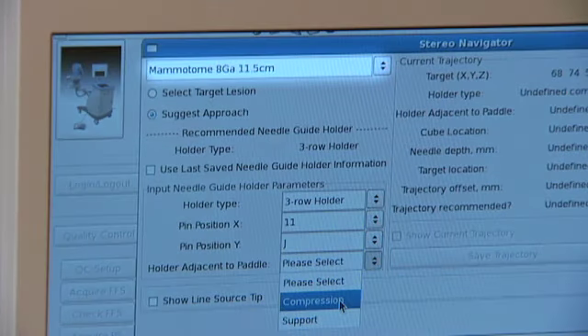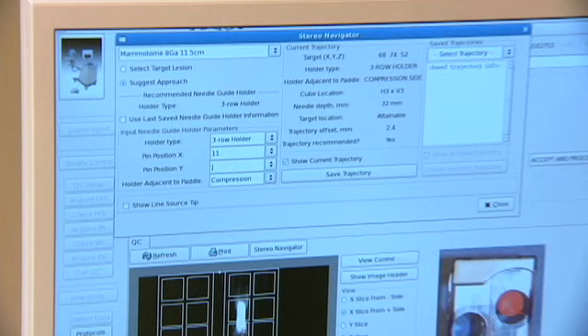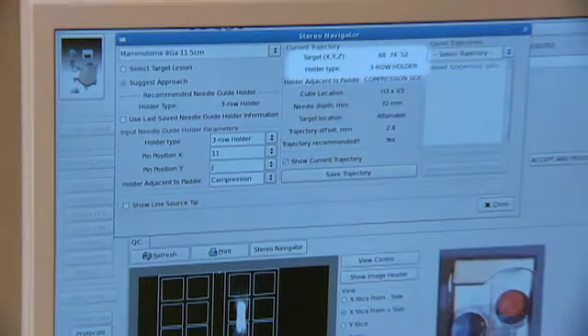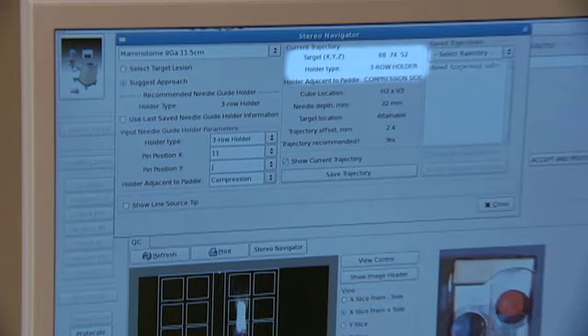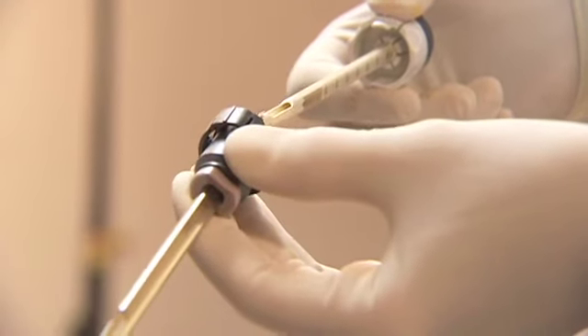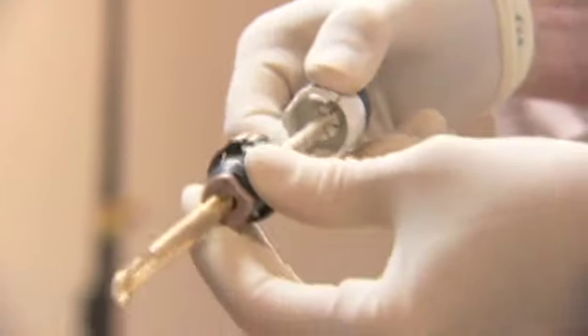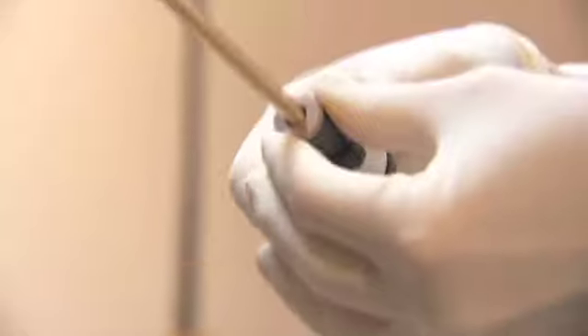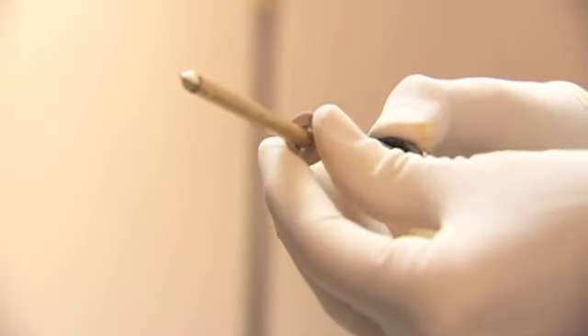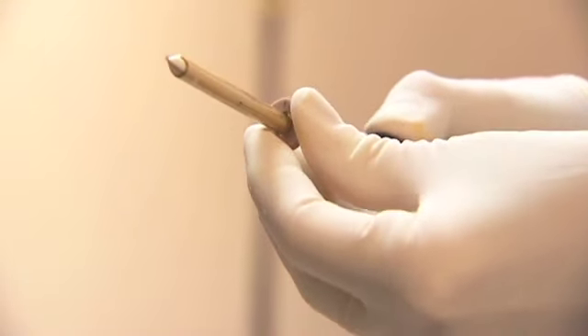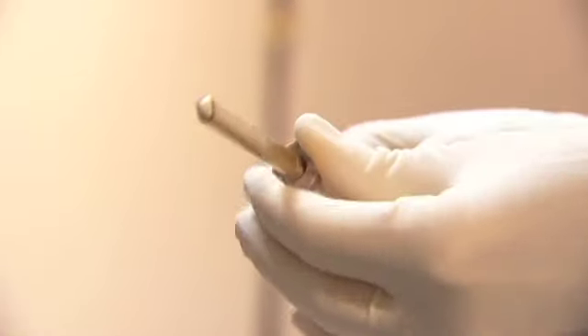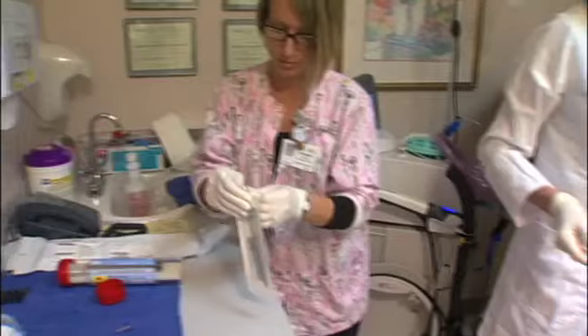Select the biopsy tool from the software menu. The Stereo Navigator software determines the 3-dimensional X, Y, and Z coordinates. Set the Z depth of the targeting set with the indicator on the distal or patient side of the Z-lock. Turn the Z-lock clockwise 1/4 turn to set the Z depth. Turn counterclockwise to adjust or remove the Z-lock, and then set aside.